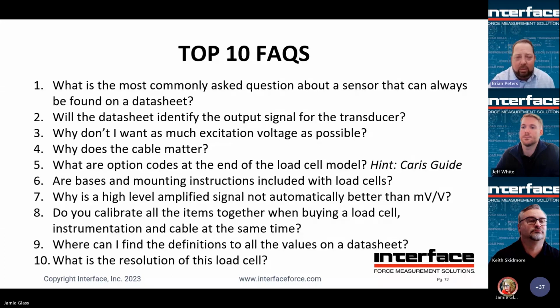However, we can certainly calibrate all the items together on the load frame hooked up. That'll remove a few layers of the error budget, if you want to think about it that way. In that now the reported value is going to primarily come down to the uncertainty of our load frame and our A2LA accreditation in terms of scope. So you'll automatically get total system performance down in the 0.04% type range if it's good components that you're using there. So where can I find the definitions to all the values of the data sheet?